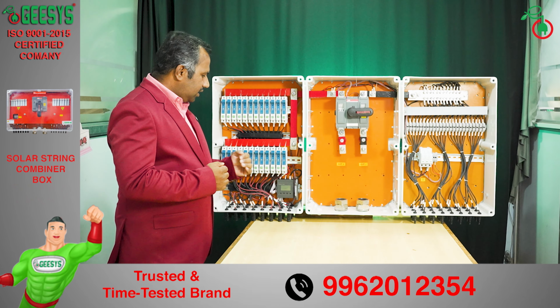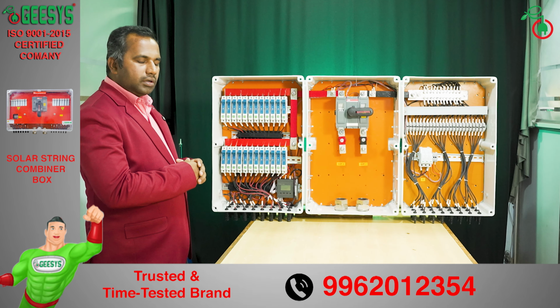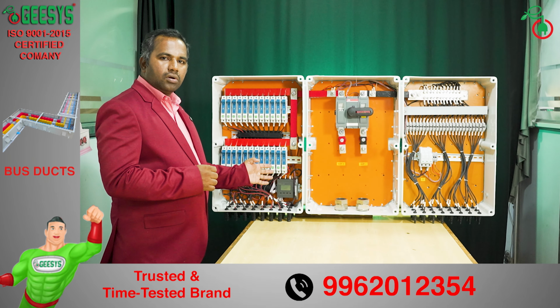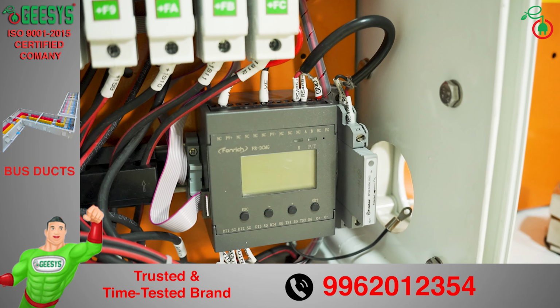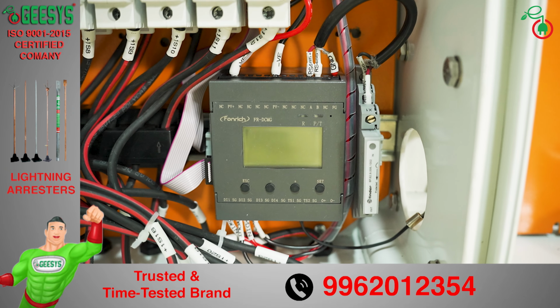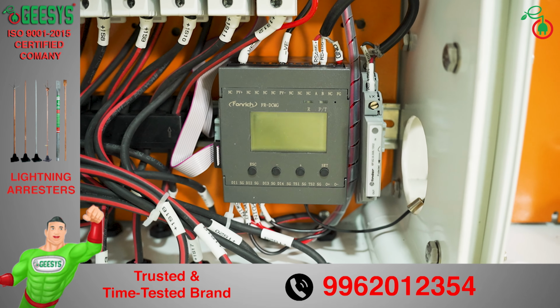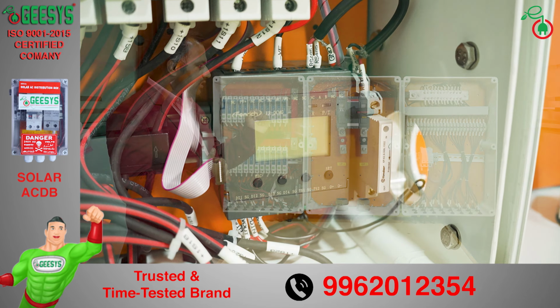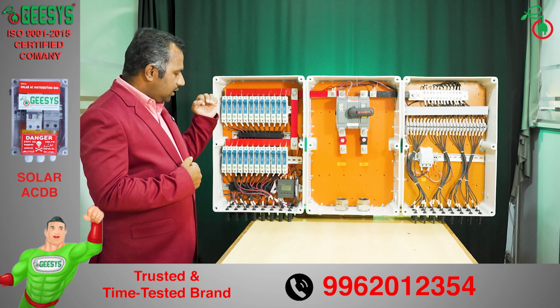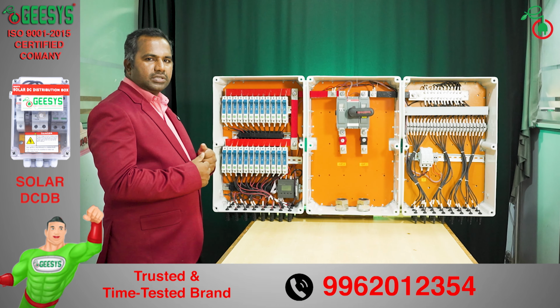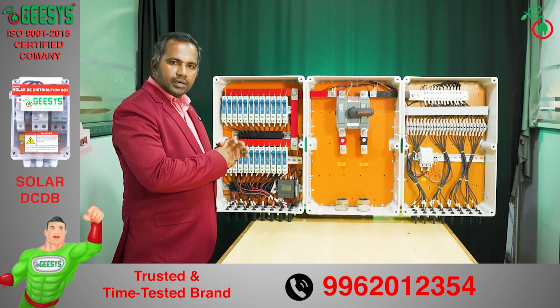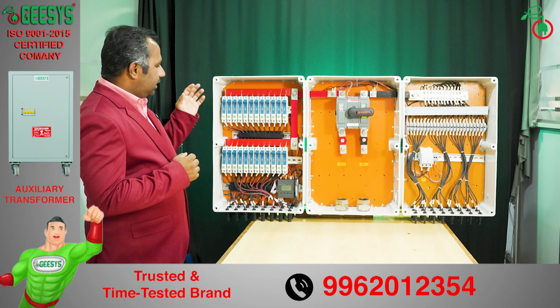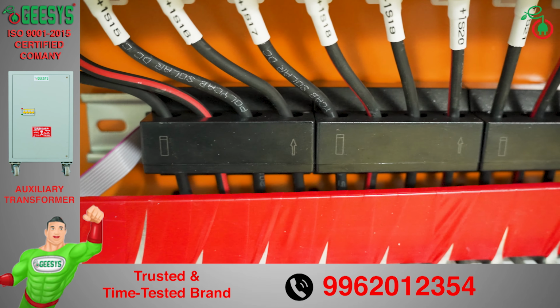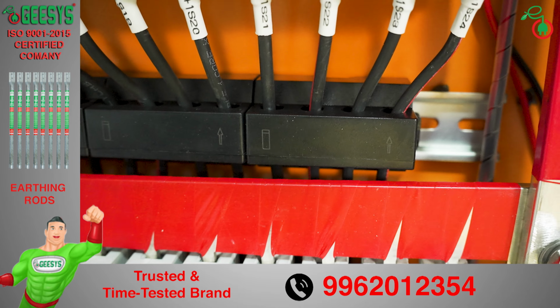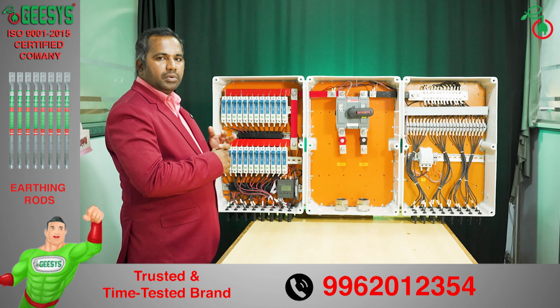And next we will see the string monitoring control card. This is the motherboard or main control card of the string monitoring unit. This unit will collect the data from Hall effect sensor, which is Hall effect based CTs, and from the status of DC switches, status of SPDs, and the temperature inside the box and temperature outside the box. All these data are collected and displayed here. And the next we have used Hall effect CT. This is Hall effect CT which collects the actual current ampere of each strings.